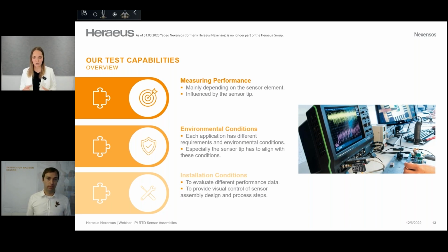So again, let me use the image of a puzzle. Here we have three different puzzle parts: the measuring performance, the environmental conditions, and the installation conditions. Let's start with the measuring performance. Here, mainly, it's depending on the sensor element, and it's influenced by the sensor tip. When we come to the environmental conditions, actually each application has different requirements and environmental conditions, and especially the sensor tip has to align with these conditions. And when we install the sensor assembly, we have the installation conditions, and we need the test capabilities to evaluate the different performance data and to provide visual control of sensor assembly, design, and process step. So let me now jump into each one of those puzzle parts.